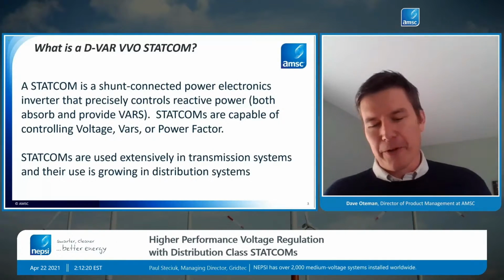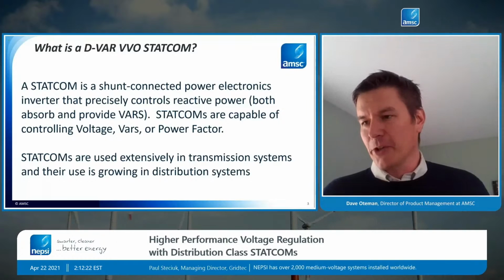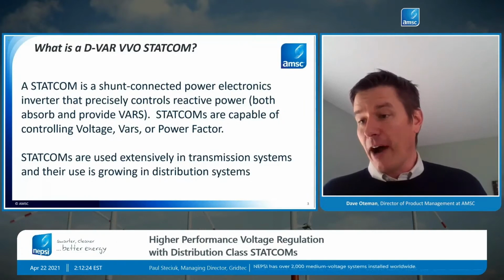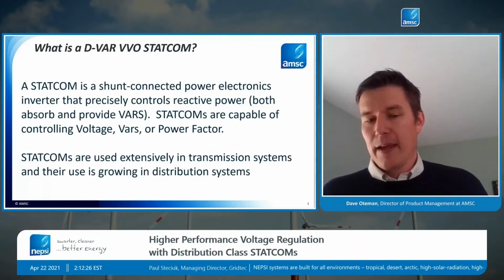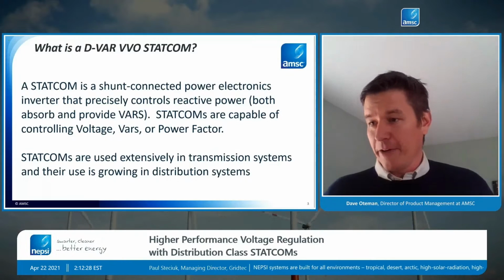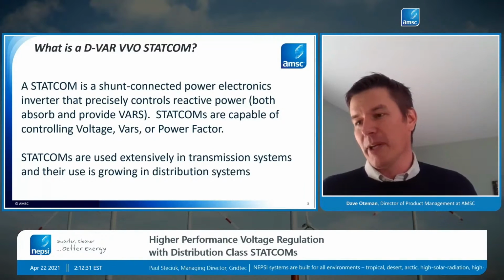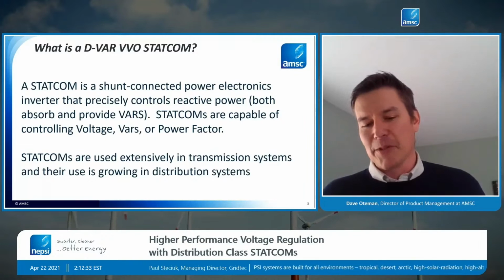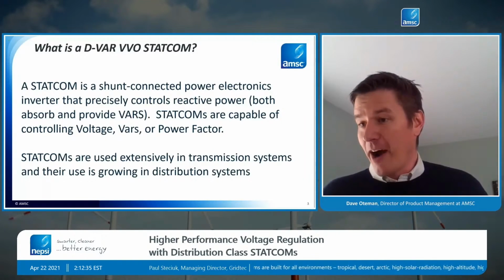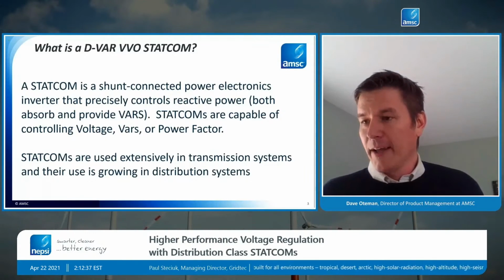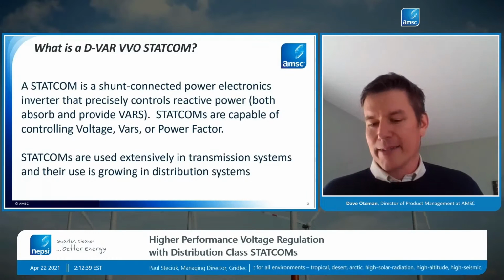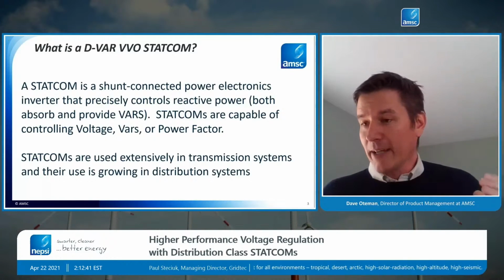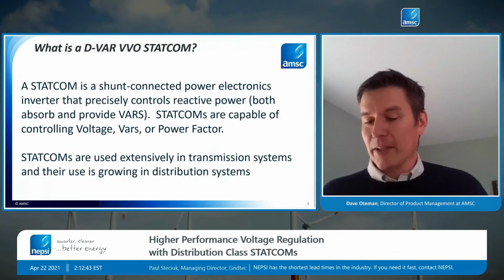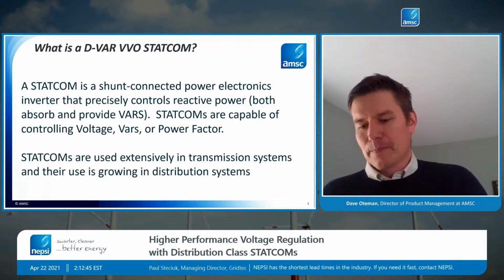STATCOMs can be used for three different purposes: controlling power factor or VARs directly in the feeder. The bigger focus of today's talk is actually how we use these STATCOMs to control voltage — those VARs that can be absorbed or supplied dynamically by a STATCOM can then directly be used to regulate voltage as well.